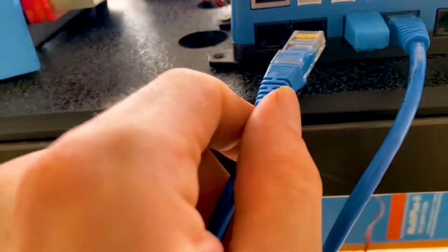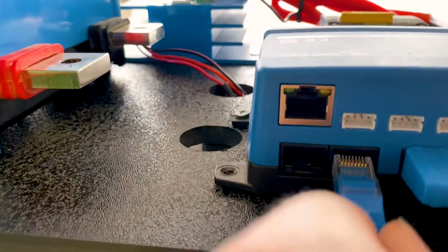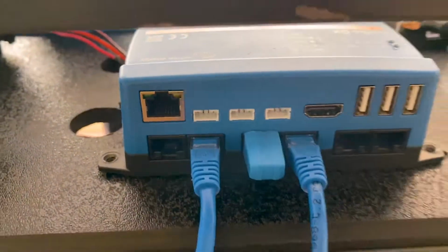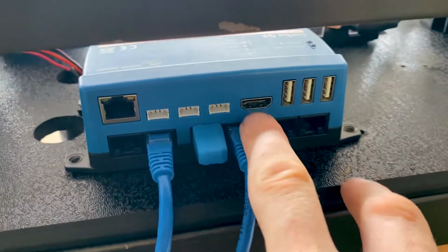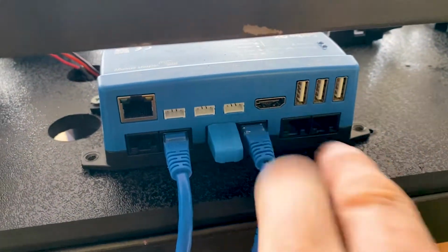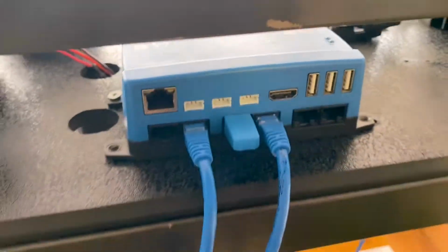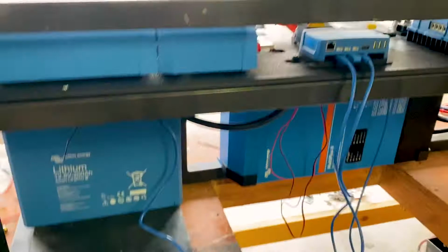That'll be your master on-off. We've got the two RJ45 cables, one from the inverter which gets plugged into the VE Bus port. The other one, notice how it's terminated, that's essential. The other RJ, that one right there, is run to the BMS. And then we've got the port for the GX Touch 50.